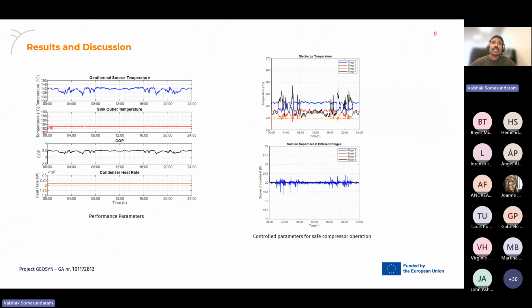And the objective of the heat pump is that it needs to provide steam at a constant outlet temperature. In this specific case, it is at 183 degrees centigrade. And as I mentioned earlier, this is achieved through modulating the speed of the compressor. And here we can see that for the dynamic varying input, we are able to maintain the sink outlet temperature as required. In addition to that, the required heat load of 2.1 megawatt is also achieved.